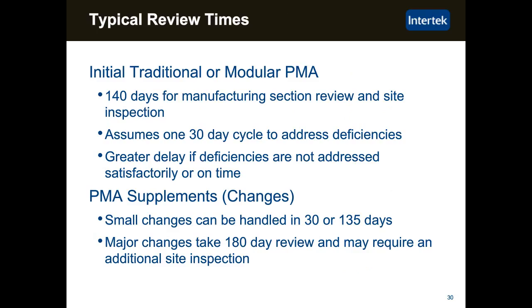So what are the typical review times once you make the submission? Well, for a traditional or modular PMA, you're looking at 140 days for the manufacturing section review and the site inspection. And that assumes one 30-day cycle to address deficiencies. Now, greater delay will take place if you do not address the deficiencies in a satisfactory or timely manner. So a quick note, a traditional PMA has all the information supplied at one time.